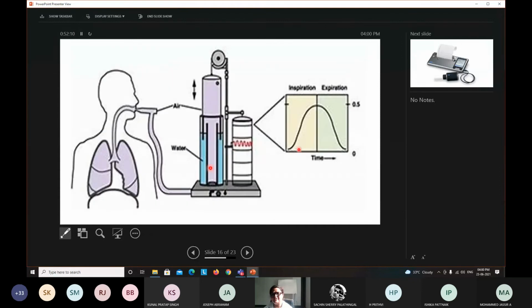I was talking about the graph paper which is pasted on the cylinder. The cylinder, that is called the kymograph drum. This is called a kymograph. This will be run by a motor. That will be a separate equipment. You will see it in our laboratory. So it will be running on the motor, and this will rotate, and it will have different speeds. These knobs are used to adjust the speed. Slow speed is 2 millimeter per second, and the fastest speed is 17 millimeter per second.